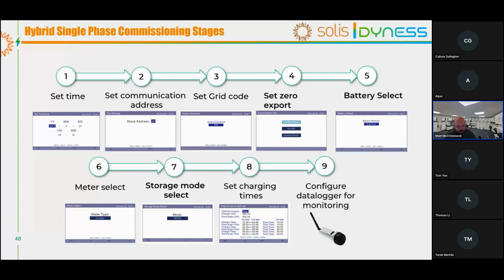So if you're having issues with your data logger, then the first thing we would probably check is the address on the inverter. Grid code, another massively important setting. If you don't have the correct grid code setting, then you could have over voltage alarms or alarms based on frequency, etc. So if we tend to see any issues with the grid in terms of alarms, then the first thing we do is make sure that you set the correct grid code. You'd be surprised at the amount of times that actually is the issue, but ultimately that's what we do.